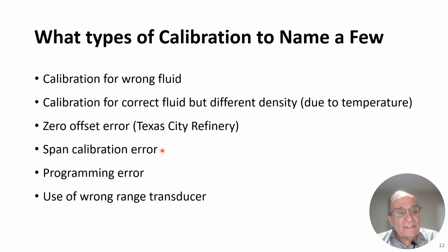Then there's span calibration error. Is that 50% when you're getting 12 milliamps? Is that really 50%? So it's got to be calibrated across the span, all the way from 0, which would be 4 milliamps, up to 100% level, which would be your 20 milliamps. And then you could have a programming error, which is when the operator puts in the wrong factors associated with programming the equipment, or the use of the wrong range transducer. Imagine using a 0 to 100 psi transducer on a tap that's only going to see 0 to 5 psi. That would certainly be an error in the setup of the instrumentation.